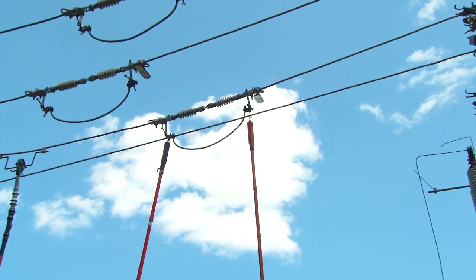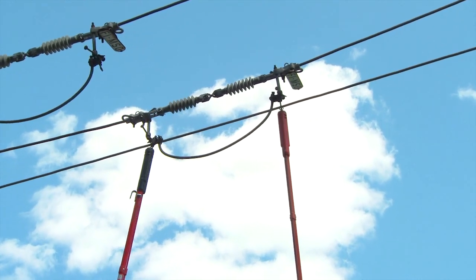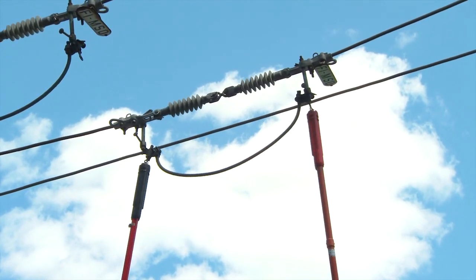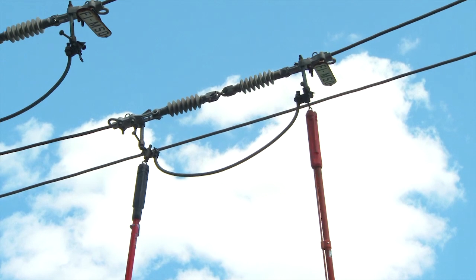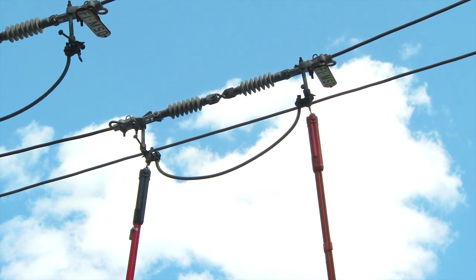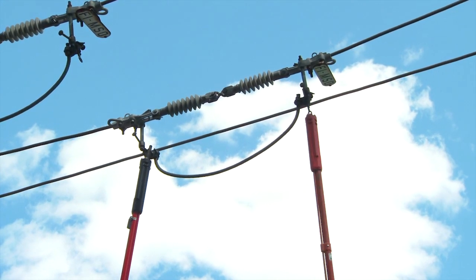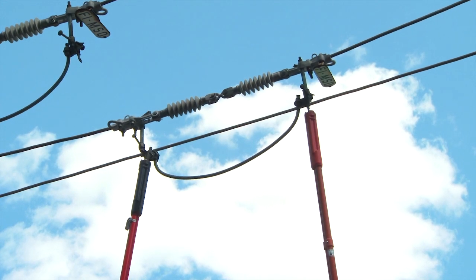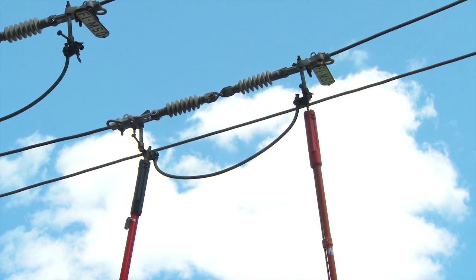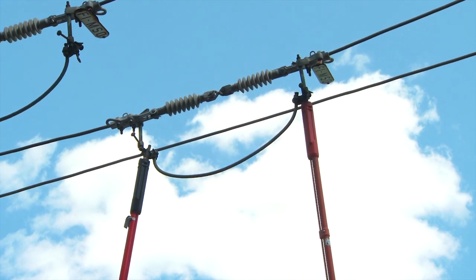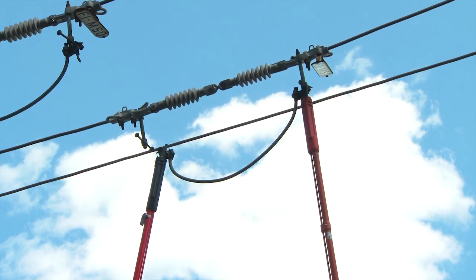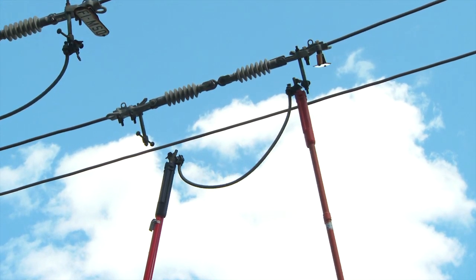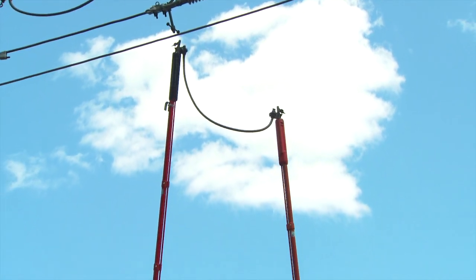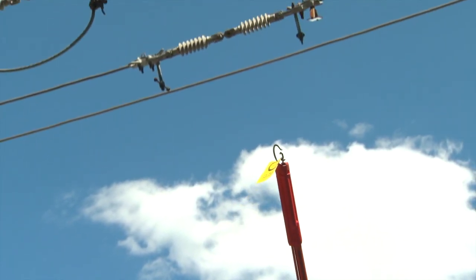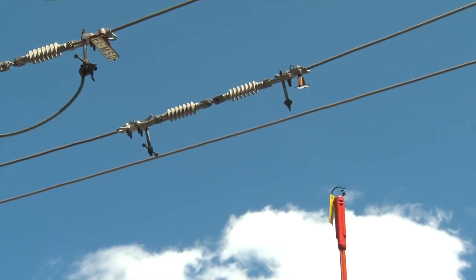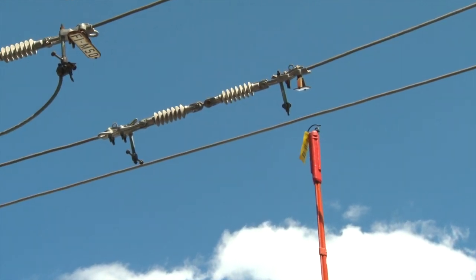Different station configurations will require the opening of live line loops, switches, or mid-span openers to completely isolate the DS. This station has MSOs on the low-voltage feeders that need to be opened. Establish a work permit on the DS if required and hang work protection tags.